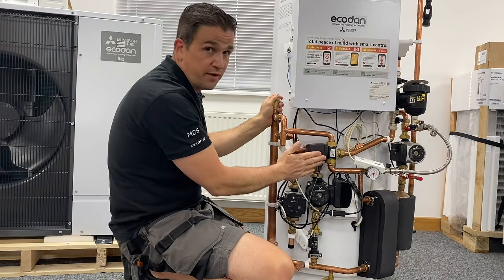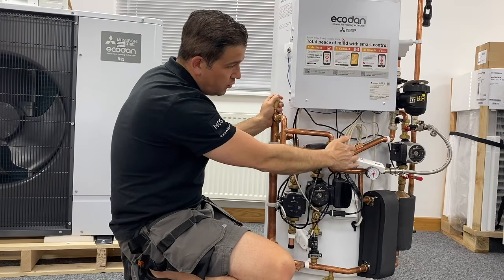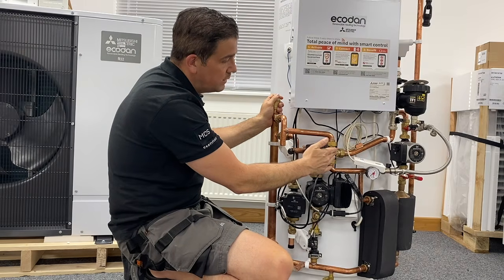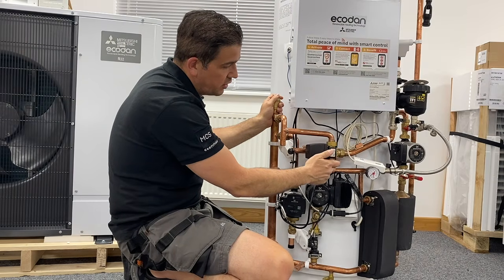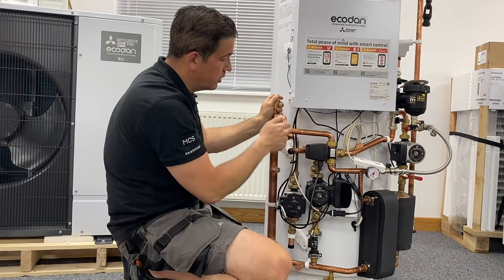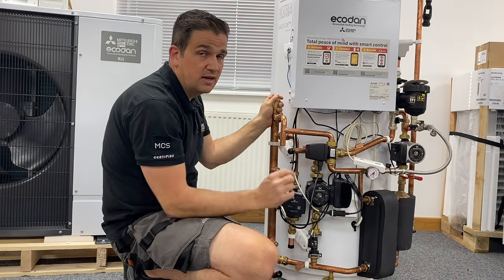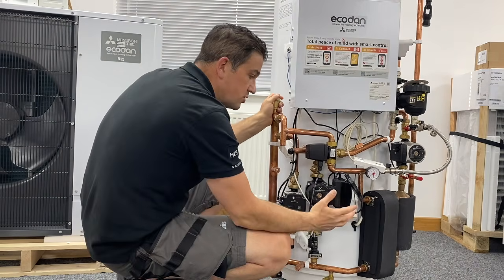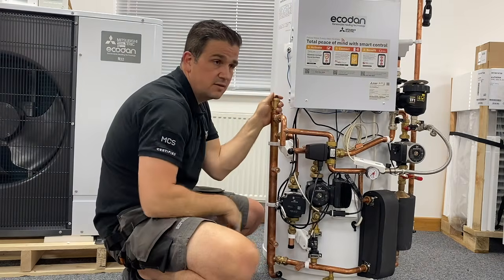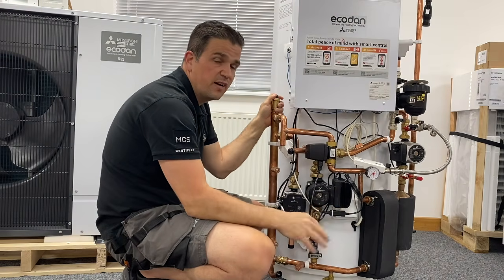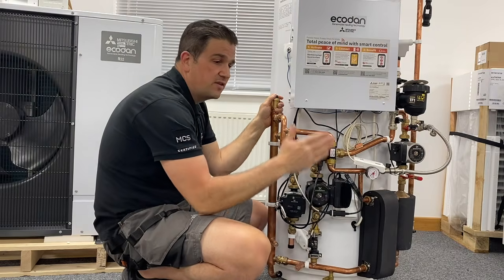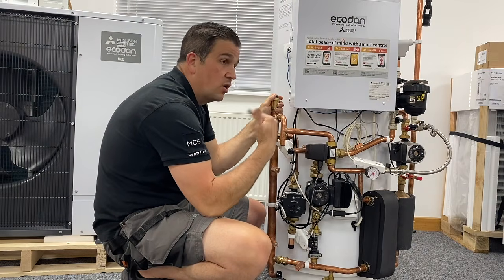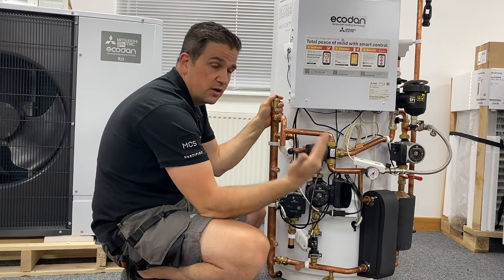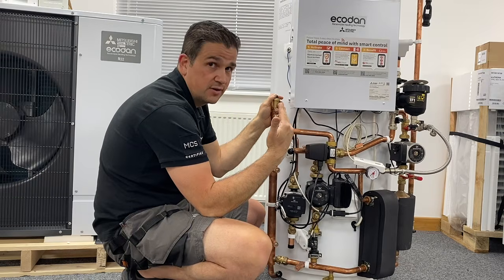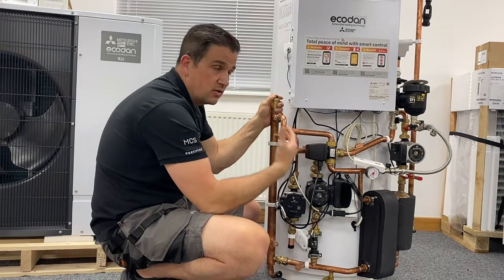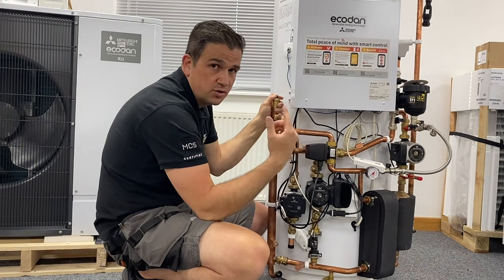This is just a simple diverter valve. So our hot water incoming from the heat pump will either go into a hot water mode or it'll come around and supply the heating. Never does both. Now on older or conventional systems, you have what we call a 3-port valve, but it's a mid-position valve. So that would mean you can either have heating or hot water, or you can have heating and hot water. Whereas heat pumps will always prioritise doing one job at a time.